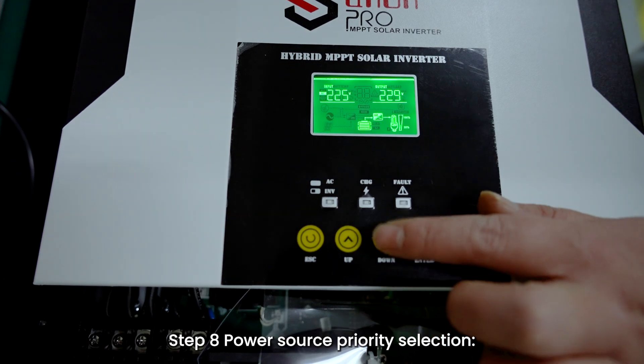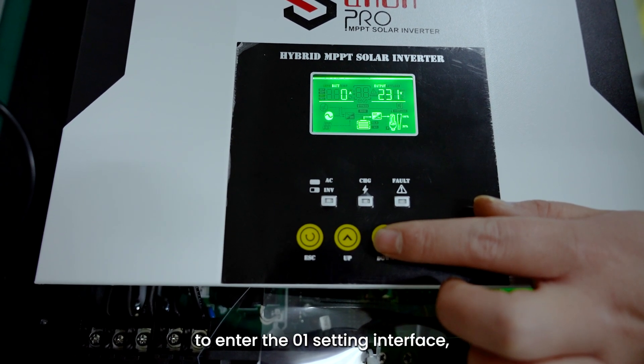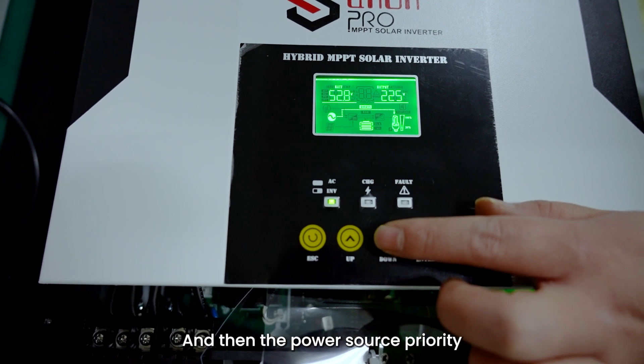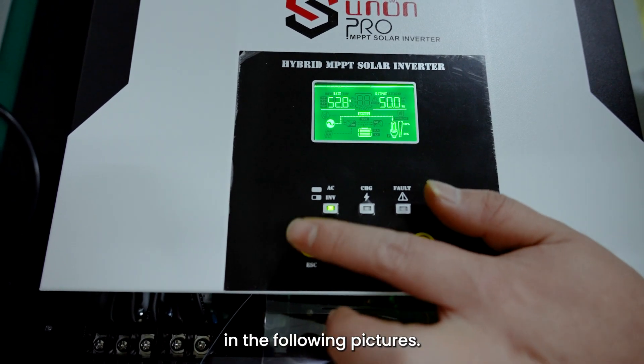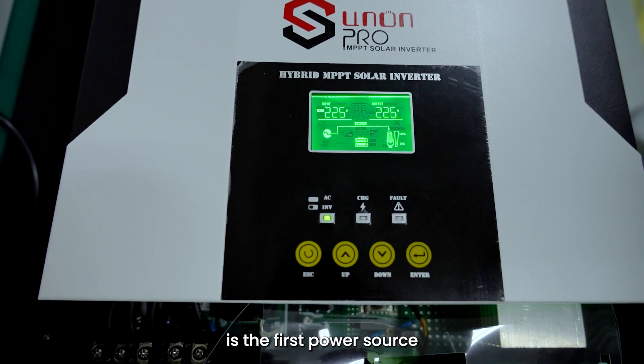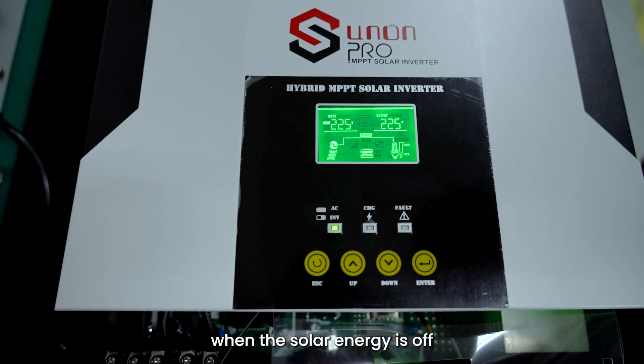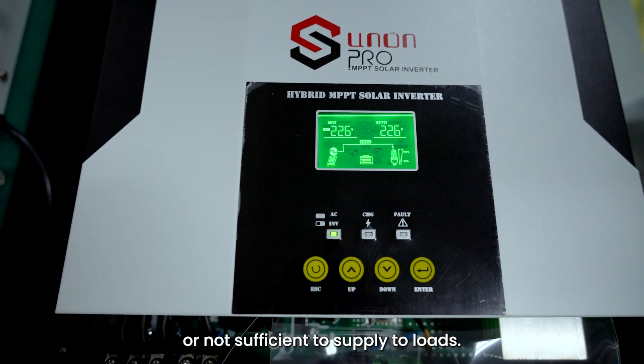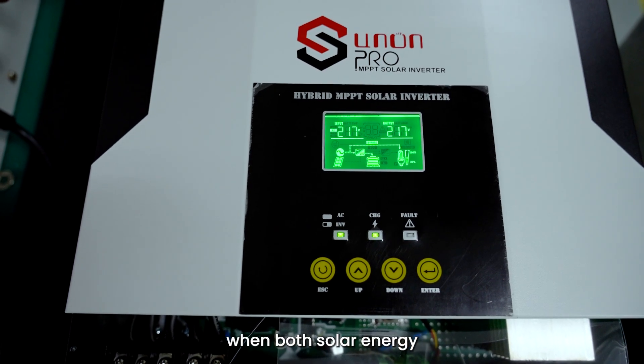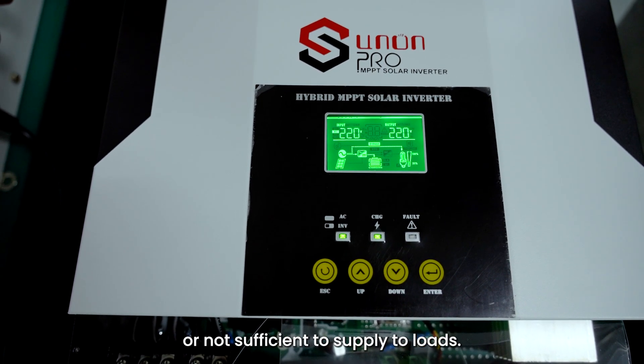Step 8: Power Source Priority Selection. Press the Enter button on the panel to enter the 01 setting interface. Press the Select button and the power source priority can be selected as shown in the following pictures. Picture 1 shows that solar energy is the first power source to supply to loads. Battery will automatically supply when solar energy is off or not sufficient. Mains will automatically supply when both solar energy and battery are off or insufficient.